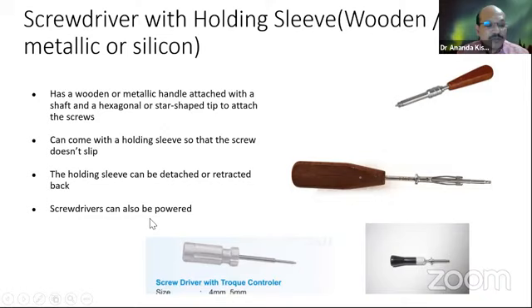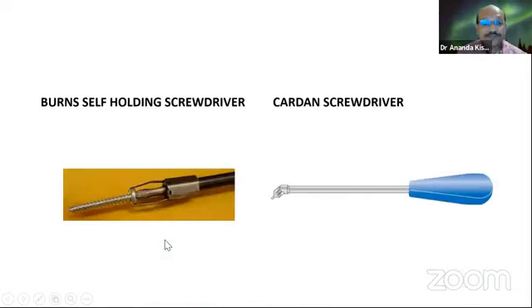Why is it important? Because torque limitation is most important, specifically with locking screws. Just after complete insertion of the screw, if we try to tighten it further, that will cause further rotation of the head in spite of the screw going further inside. That will lead to damage of the threads. So we have to limit the torque just after full insertion of the screw with the help of this torque limiting screwdriver.